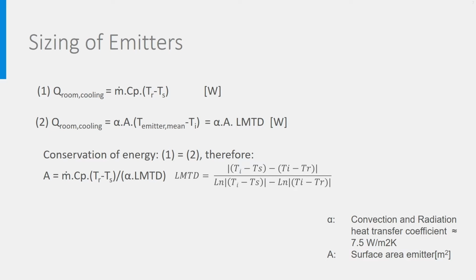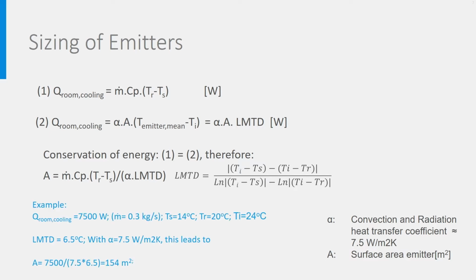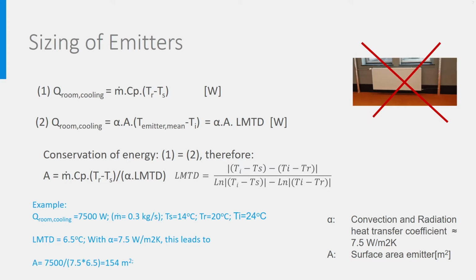If we take a new example where the room needs 7.5 kilowatt cooling, I remind you it is a large room of 125 square meter, we come to a needed surface area for the cooling panels or the cooling floor of 154 square meter. You may remember from the lecture about hydronic heating that with the same load, the needed surface area was only 20 square meter. This is because much higher temperature differences are allowed in heating mode. This is also the reason that radiators like this one are not used in cooling mode. The surface area is much too small to produce enough cooling, and cooled ceilings or floors are preferred.